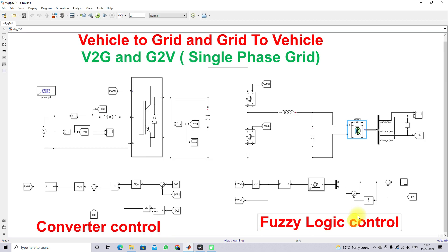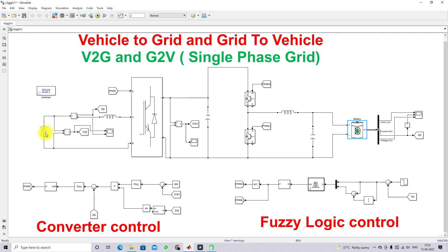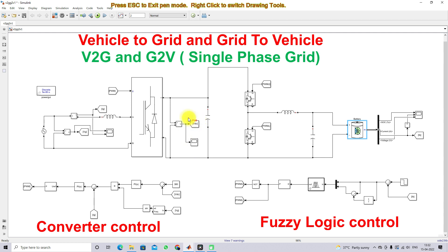The converter control logic operates in both directions. This converter is used to keep the source current sinusoidal and in phase with the source voltage. For this, we need to measure the DC link voltage and compare it with the reference voltage, which is maintained at 380 volts.